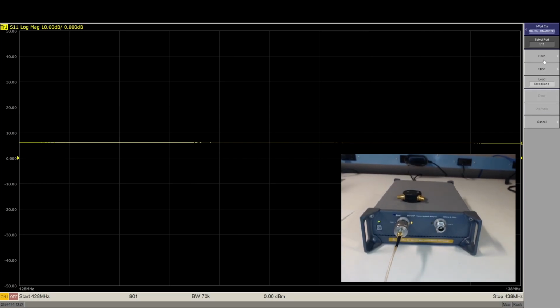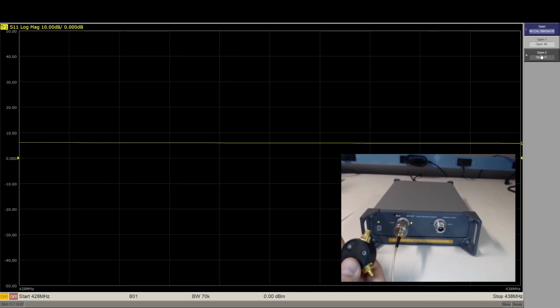Connect the part of the standard marked with an O for open to the end of the cable. Click on the Open button in the software interface, then click the Open F since the connector type on the standard is female. Next, connect the part of the standard marked with an S for short to the end of the cable.